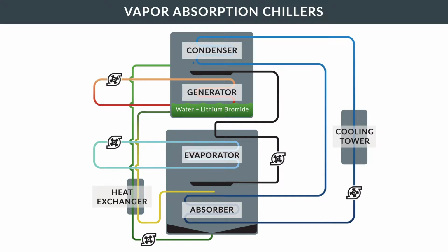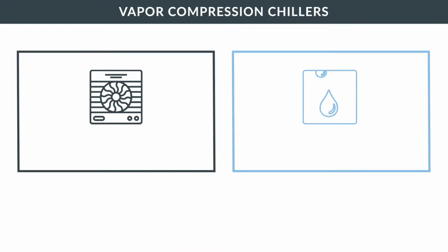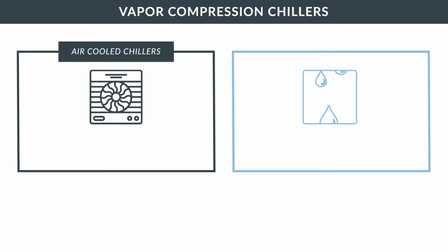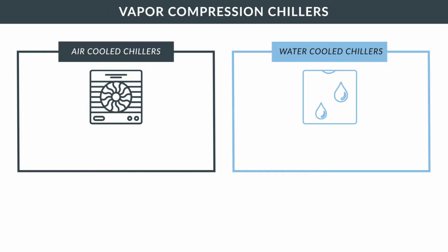Vapor absorption chillers generate less pressure and, due to the larger number of components, have a larger footprint than vapor compression chillers. We will examine in greater detail the class of chillers with more portability and flexibility: vapor compression chillers. Vapor compression chillers are most commonly used and fit into two subcategories: air-cooled chillers and water-cooled chillers.